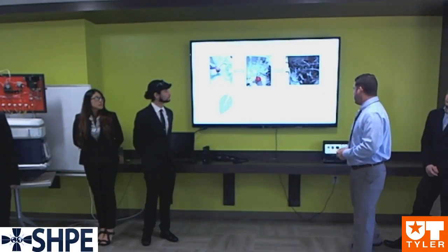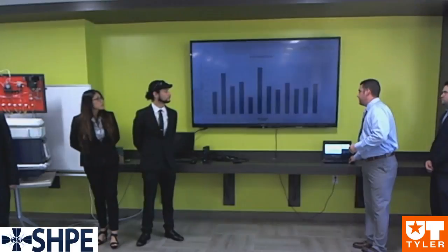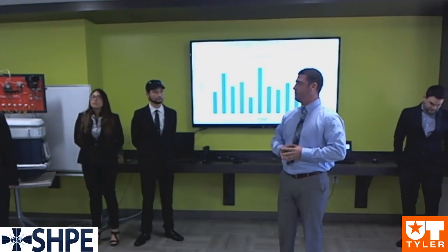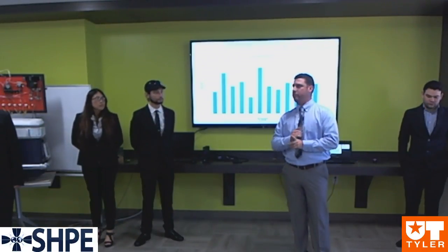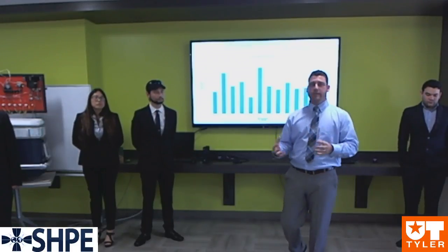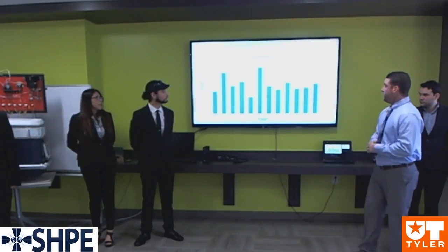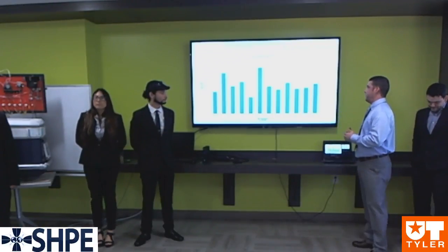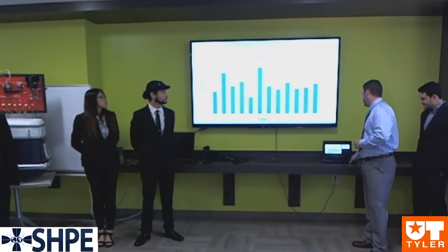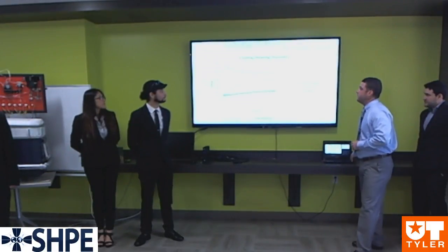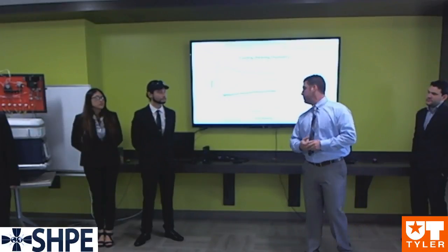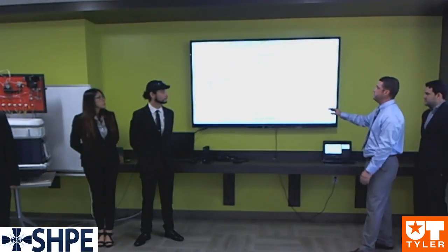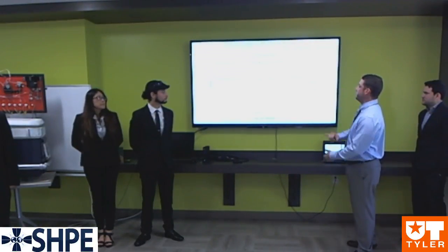Now, I want to summarize for you real quick our successes, because it is a complicated machine, and I want to highlight the fact that not only do the individual systems within it work, but the unit as a whole works together quite well. Our CO2 concentrations, when expected, spiked in the places that we expected, and we successfully read those concentrations. Our cooling, heating, humidity found an equilibrium over time. Again, our initial responses brought them to a steady state that we wanted, and over time we see that it maintained those temperatures and humidities.